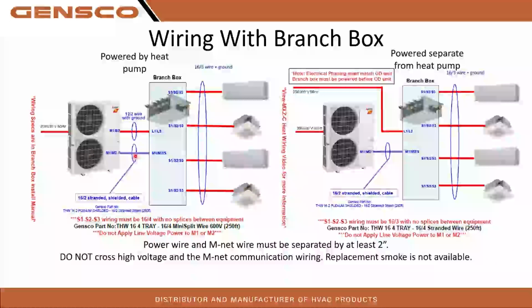I have seen guys run incorrect wire size. They'll run a 14.2 Romex cable or whatever it may be, 14.4s. I do see communication problems happening from that just randomly. And if we get that call, we go out to a site and we see that it is 14 gauge wire, not the proper 16.2, and you're having random communication problems, we will tell you to replace it. So make sure that this wire, that M1, M2, or MNet, is the 16.2 stranded shielded wire.